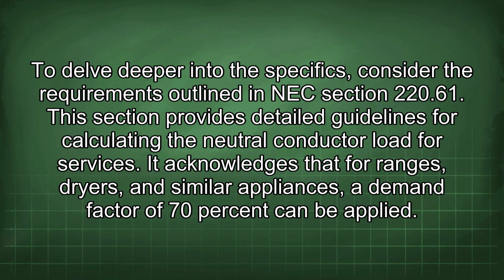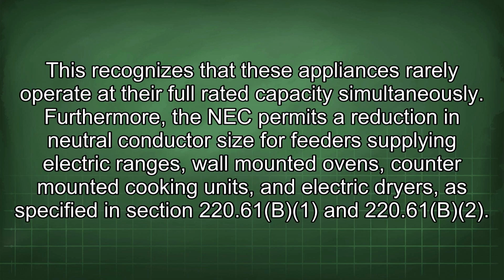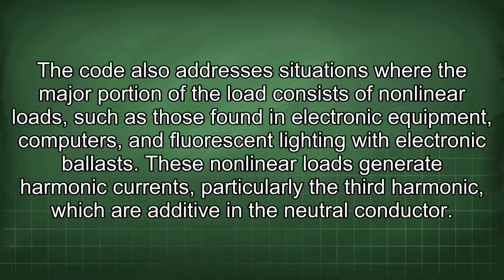To delve deeper into the specifics, consider the requirements outlined in NEC Section 220.61. This section provides detailed guidelines for calculating the neutral conductor load for services. It acknowledges that for ranges, dryers, and similar appliances, a demand factor of 70% can be applied. This recognizes that these appliances rarely operate at their full rated capacity simultaneously. Furthermore, the NEC permits a reduction in neutral conductor size for feeders supplying electric ranges, wall-mounted ovens, counter-mounted cooking units, and electric dryers, as specified in Section 220.61(B)(2).